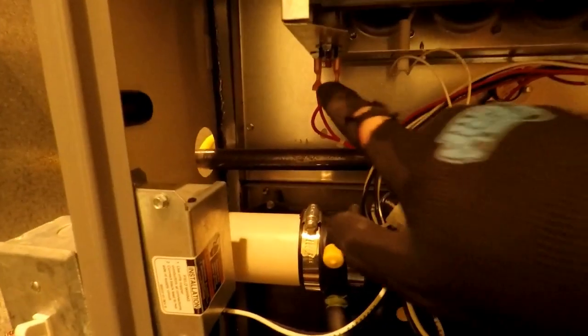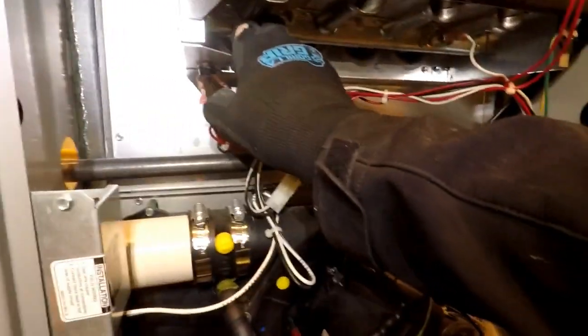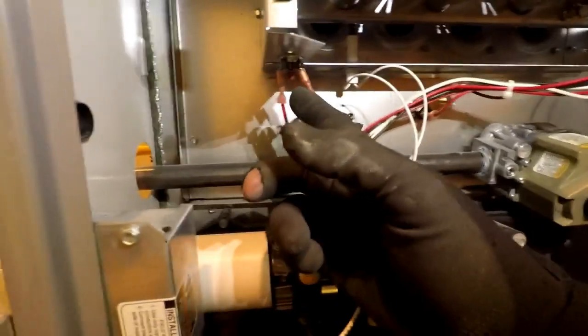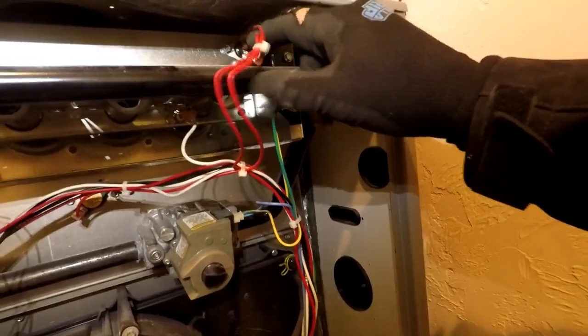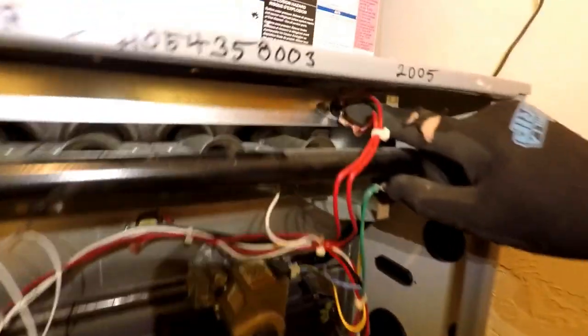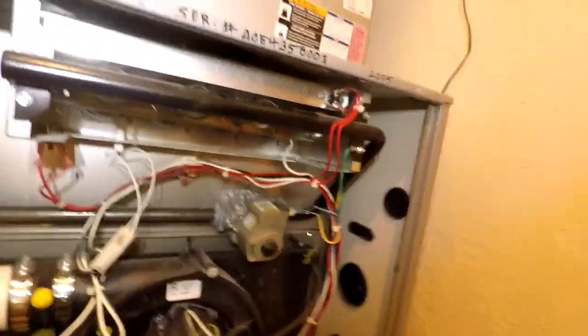Getting four flashes, limit or rollout switch open. So my rollout switches are right here and right here. And then of course my limit is right there. Let's see if one of these are tripped. You push on it, it'll snap. Not that one. Oop, that one. Rollout switch was tripped.